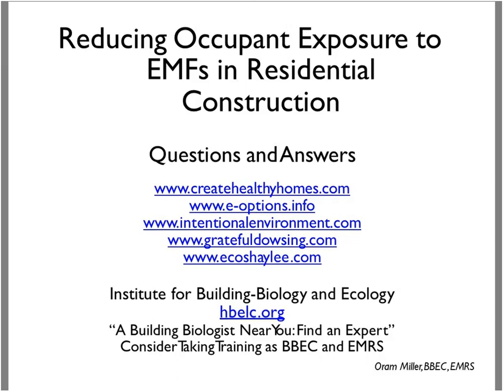Well, I can field that. It depends. First, it's very important for people on this call and viewers of this webinar to understand that metal conduit does not prevent magnetic fields. You prevent magnetic fields by having balanced loads between the hot and the neutral, and having the hot and neutral together in the same path. In other countries you can have the neutral on a different path, like in Mexico—hot over here, neutral over there—that's allowed. But in this country they have to be together, and the code says that, by the way, though it's not enforced.